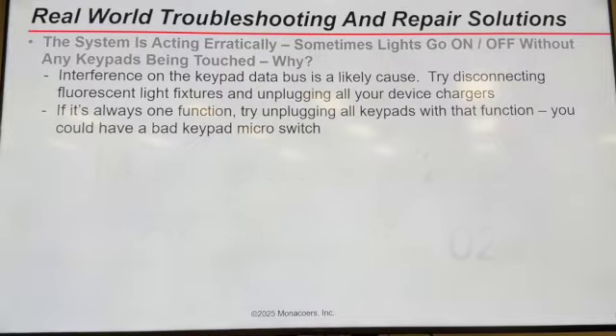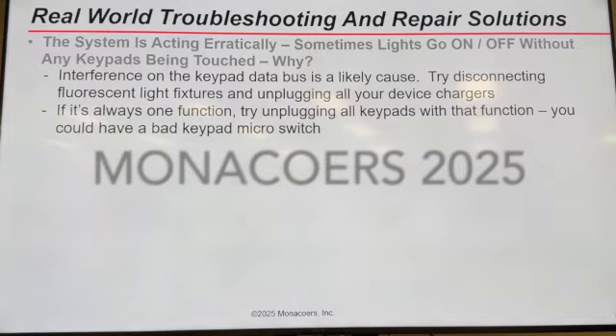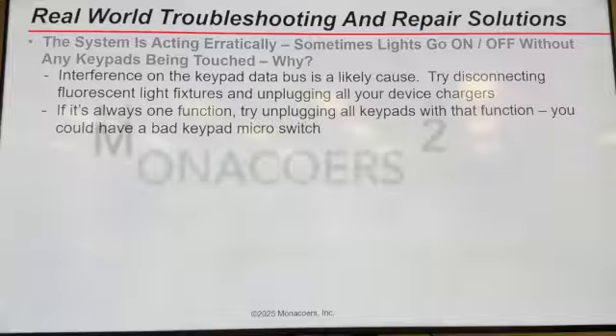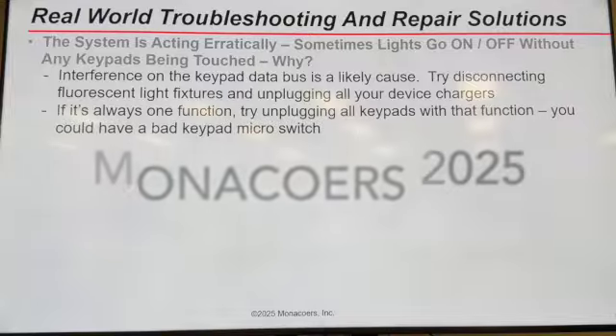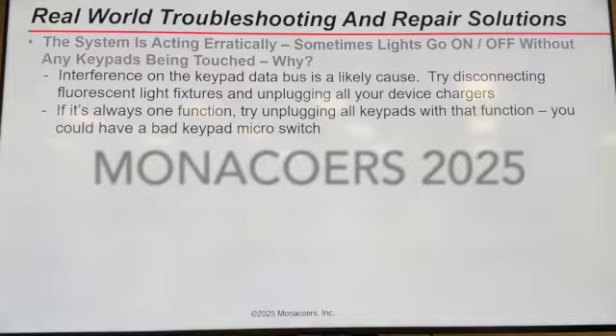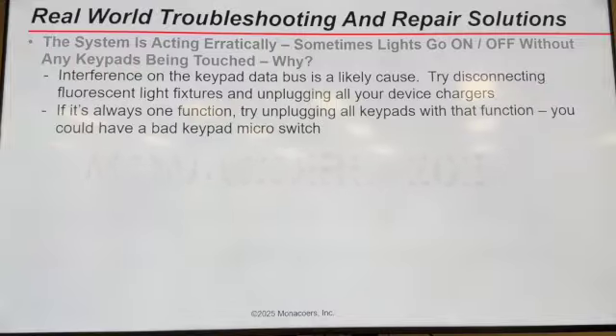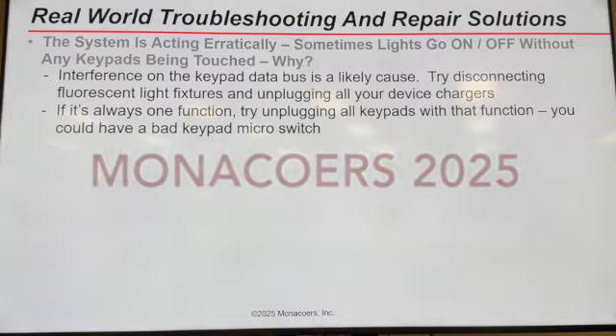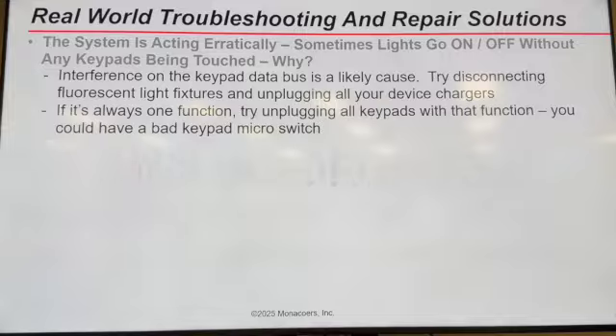The other one I saw was actually at a rally, where after some time their lights just kept going up and down, up and down. After troubleshooting, we found that one of those relay/input modules had an input - there was a switch near the door that would turn lights on - and that module was faulty. It was sensing that switch as continually being pressed, so it sent onto the bus a continuous signal to turn it on, causing a dimming signal going up and down. Replacing the module fixed the problem. So in effect, the switch was being held in because the module was bad.